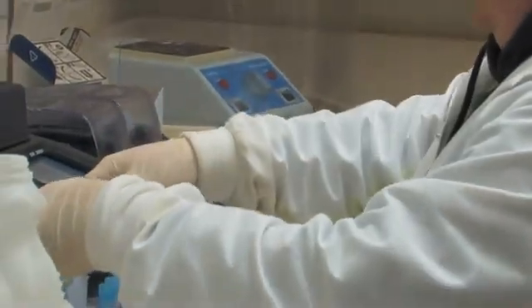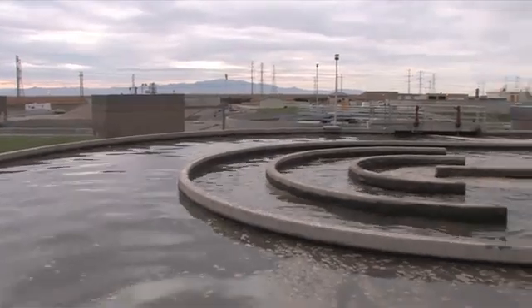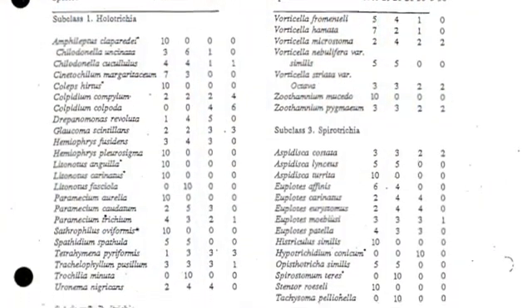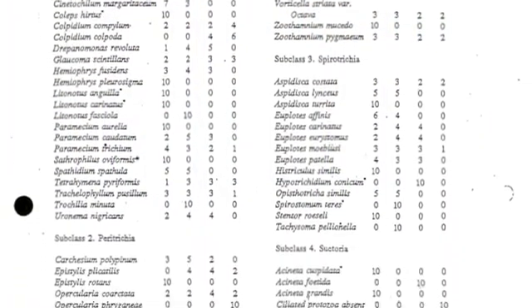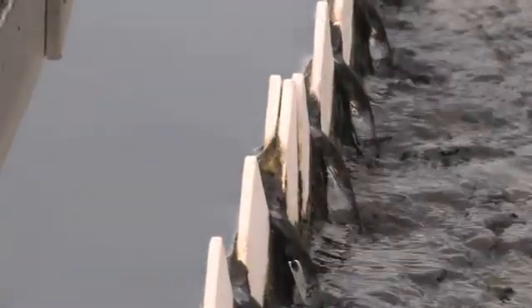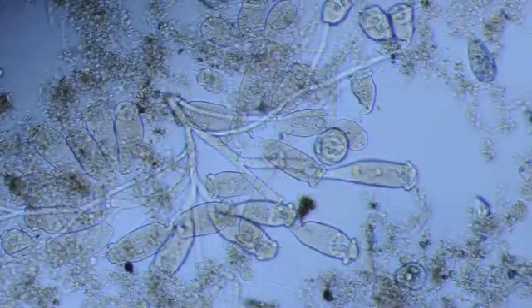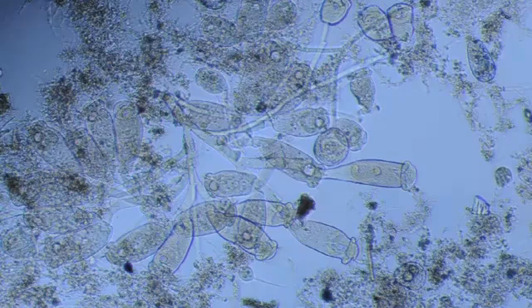Do we care who's in our process and how many there are? The answer is yes. Researchers in England evaluated the presence of ciliated organisms in treatment plants, comparing effluent quality to the organisms present. They developed a table correlating which organisms were present based upon effluent quality. For example, Vorticella and Epistylis are seen normally with high quality effluent, whereas Opercularia is seen more often in lower quality effluent.